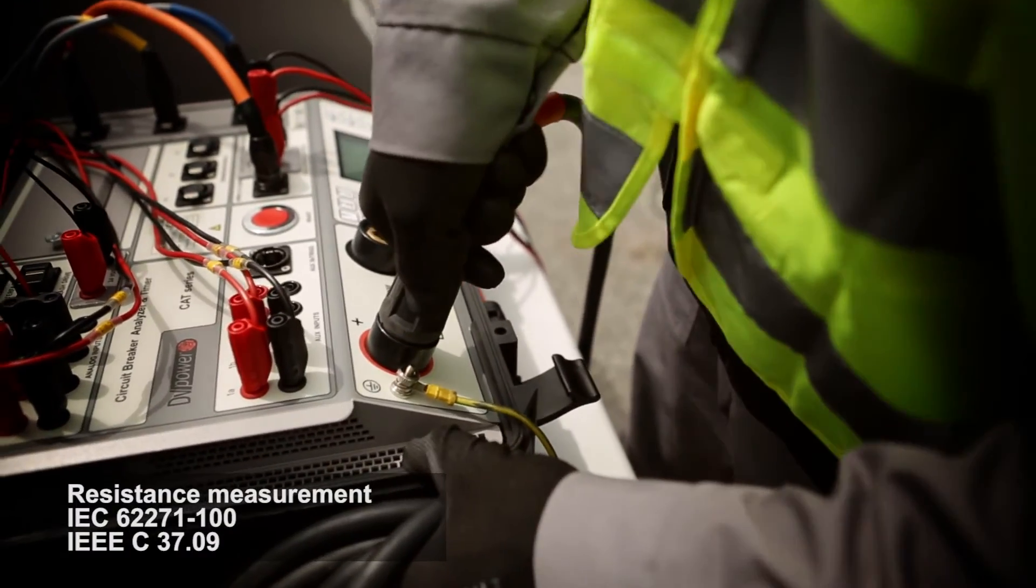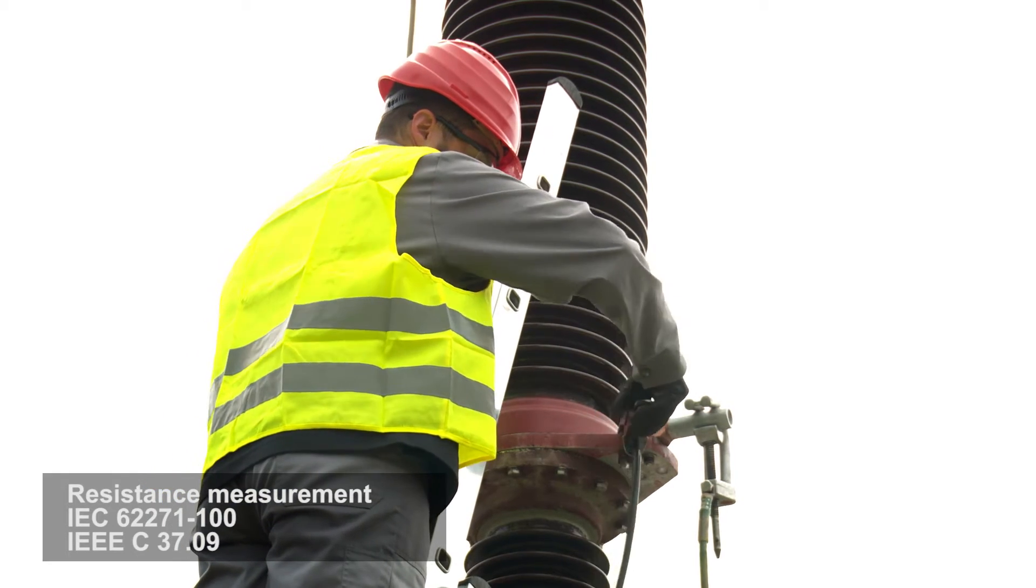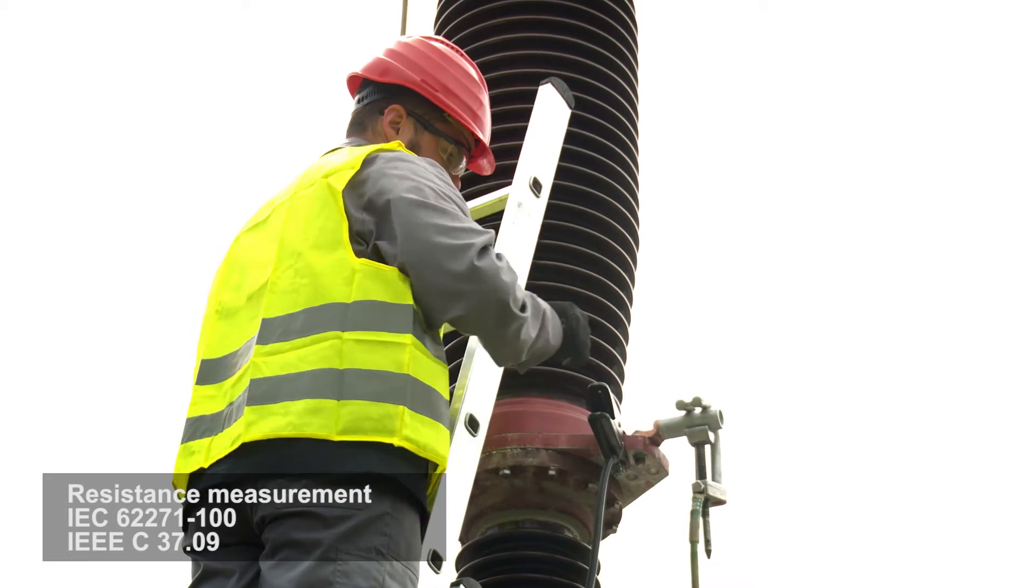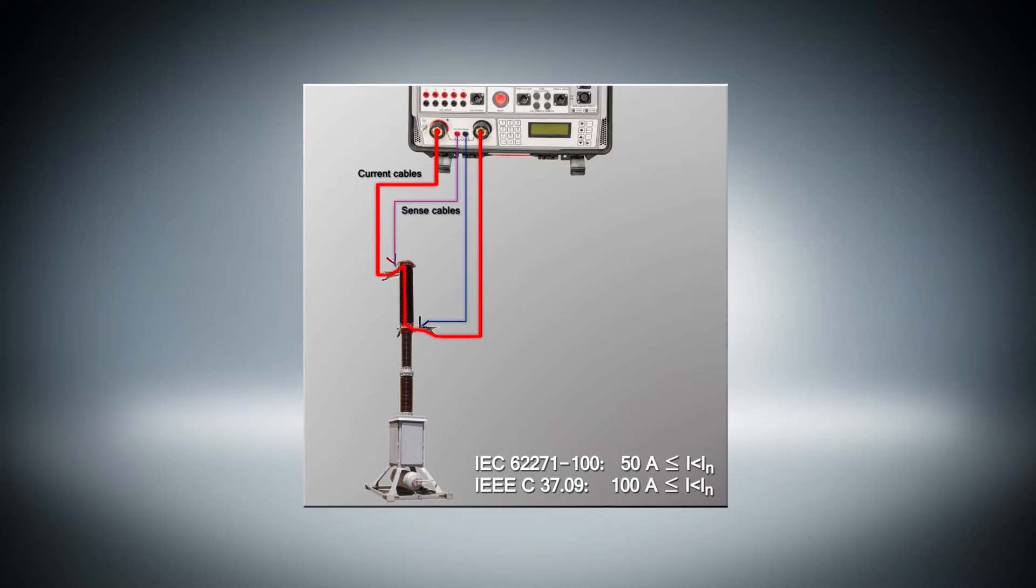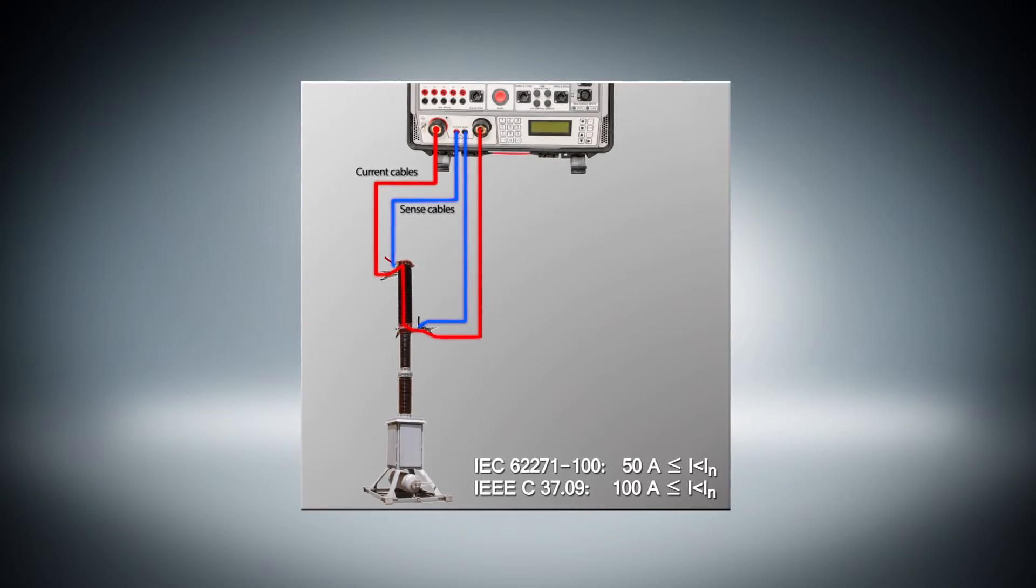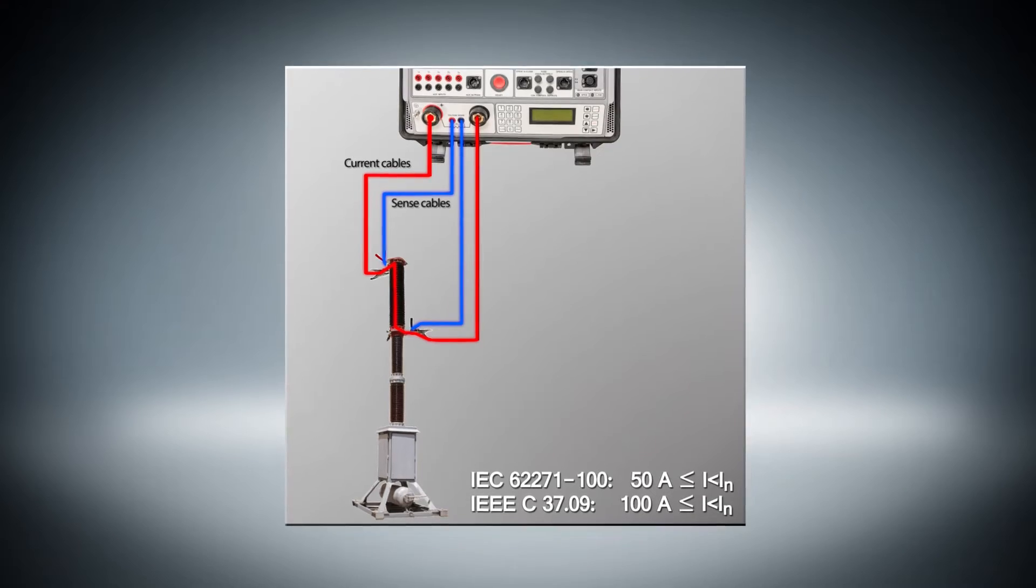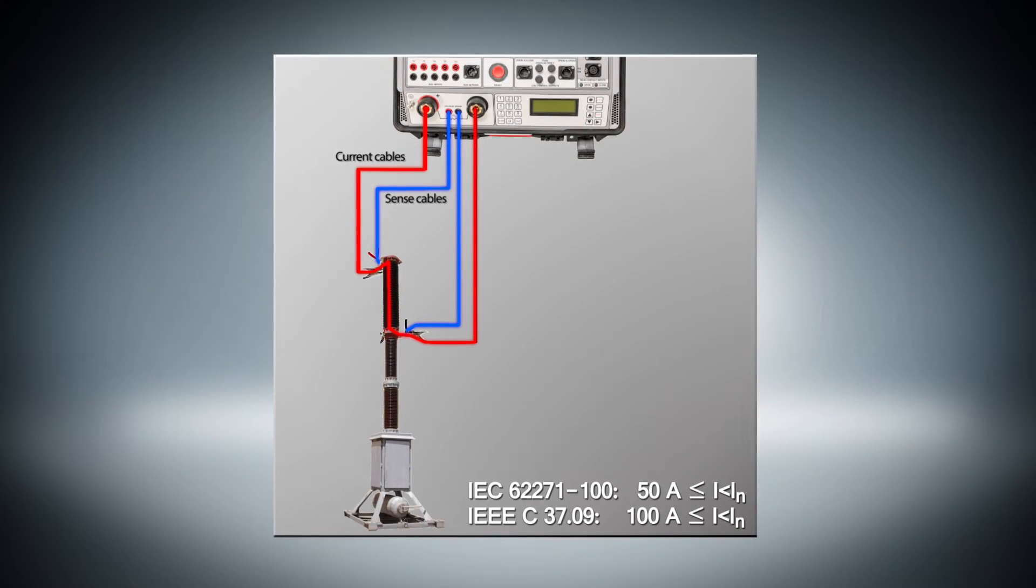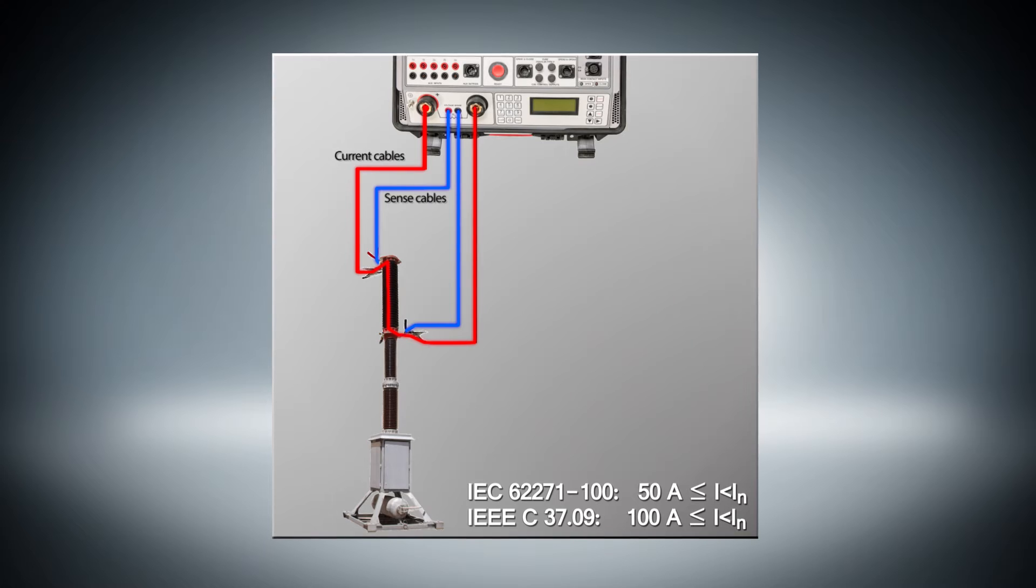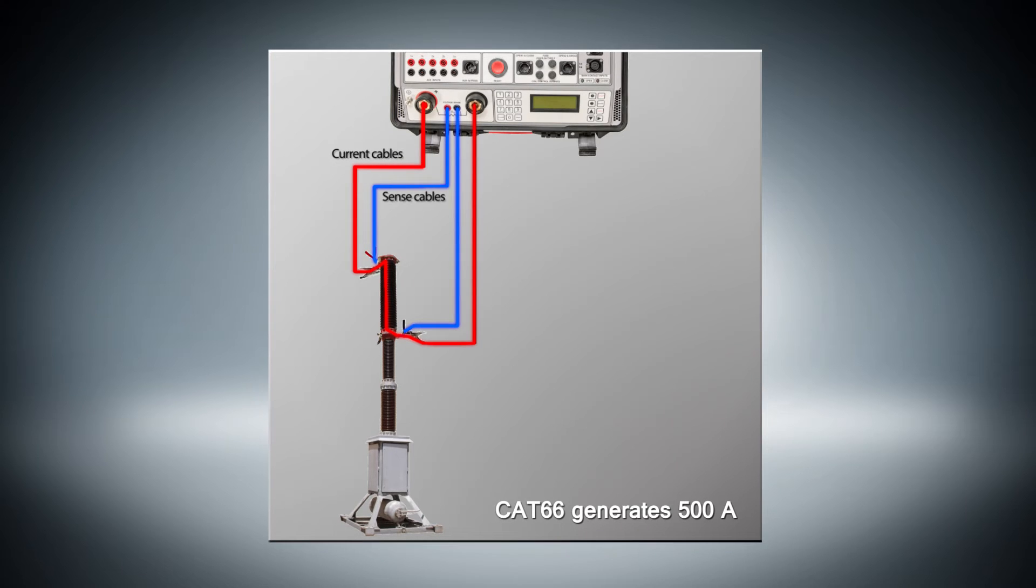Well known Kelvin's 4-point method is used for resistance measurement. DC current is generated through the closed circuit breaker contacts. The voltage drop is measured between the terminals of the circuit breaker. The resistance is calculated using Ohm's law. According to the IEEE standard, the minimum test current is from 100A DC up to as close as possible to a breaker's nominal current. The IEC standard defines the test current in the range from 50A DC to the rated circuit breaker continuous current. CAT66 can generate 500A during a contact resistance measurement test.